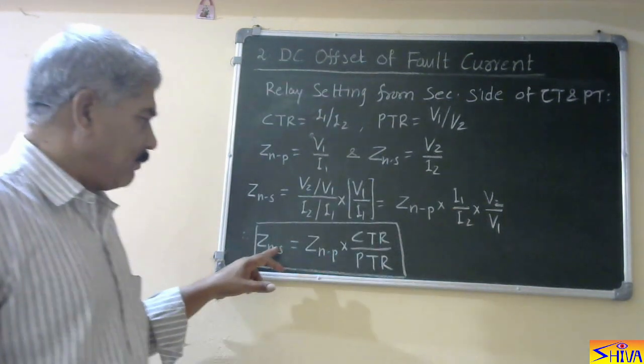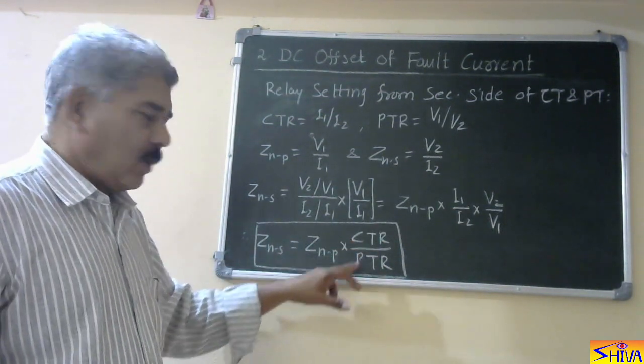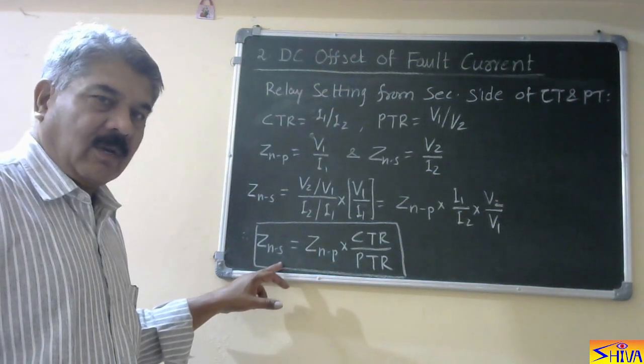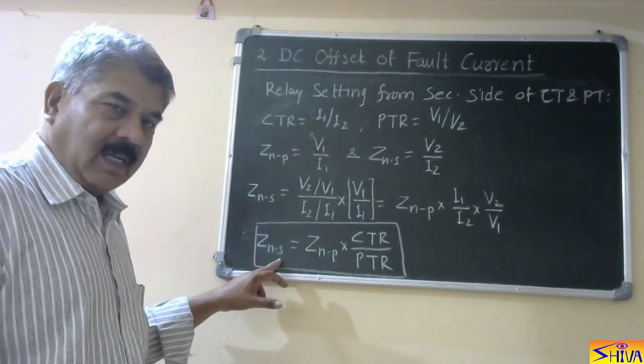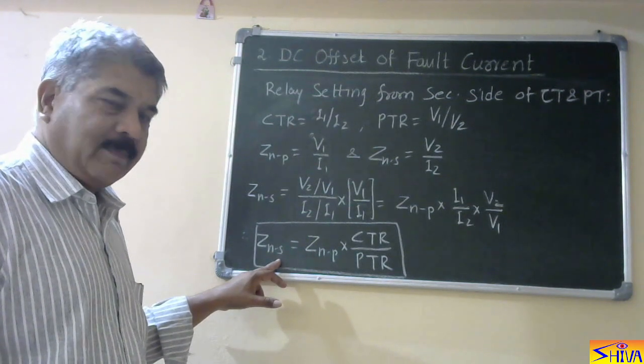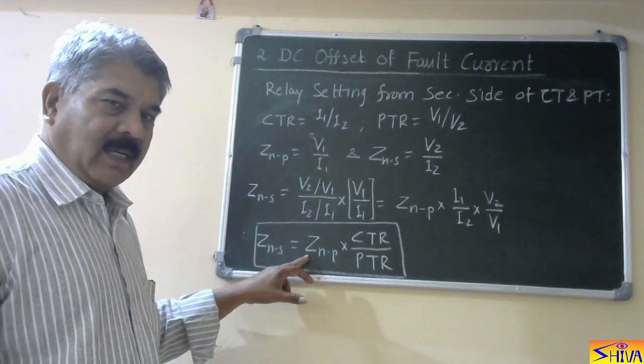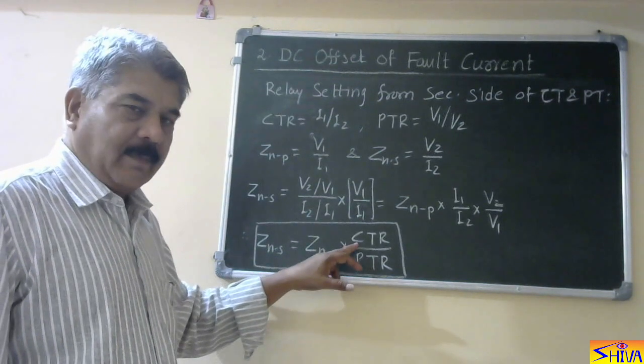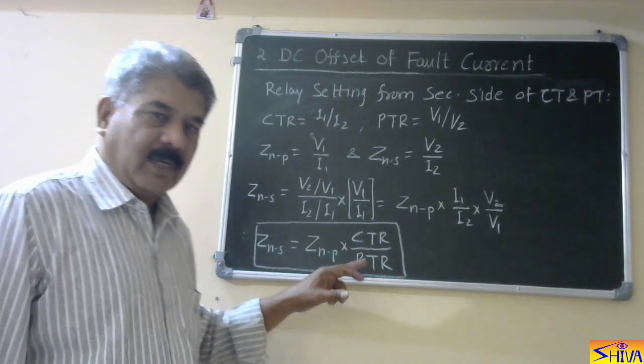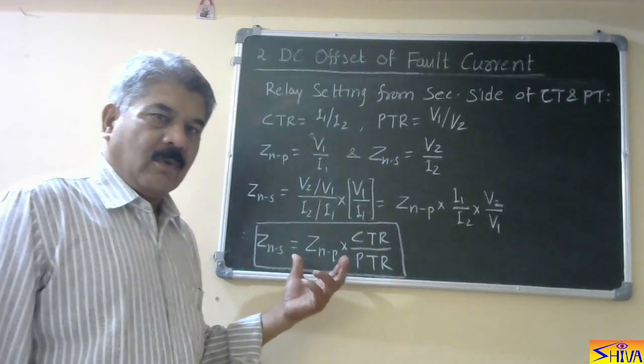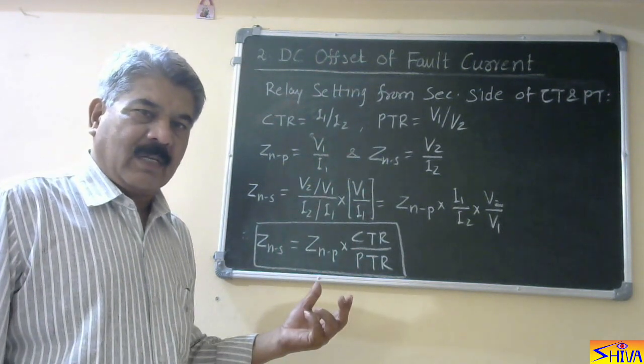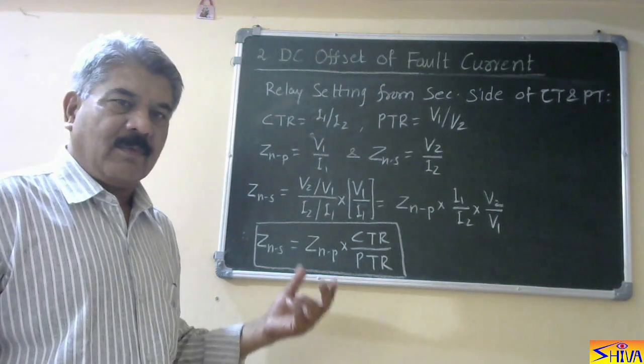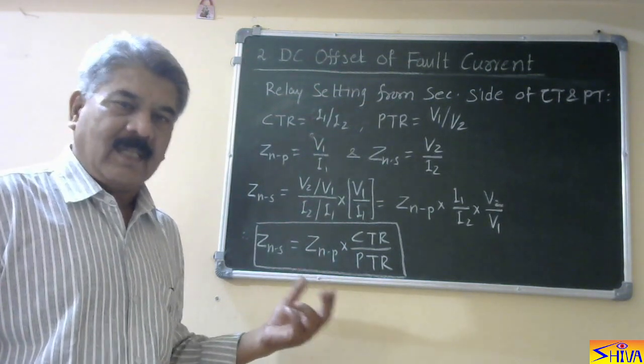So this is nothing but CT ratio upon PT ratio. The impedance setting or reach of the relay from the relay side — that is the secondary side of CT and PT — is equal to the reach from the primary side multiplied by CT ratio upon PT ratio. So whenever CT ratio and PT ratio are given, we compute the setting of the relay from the secondary side, that is relay side.